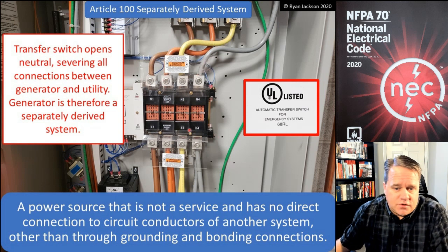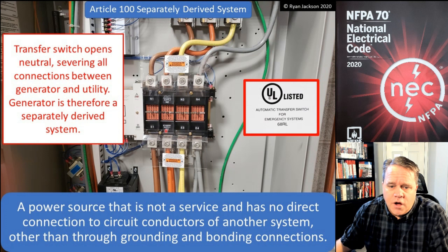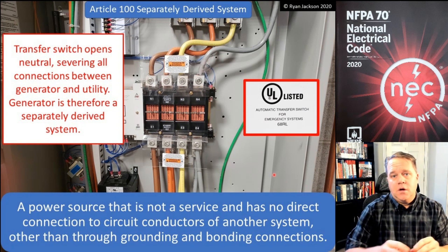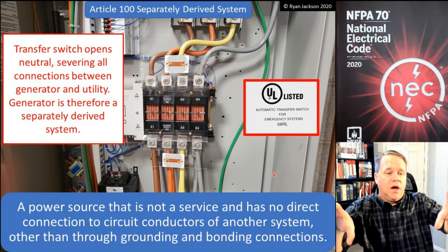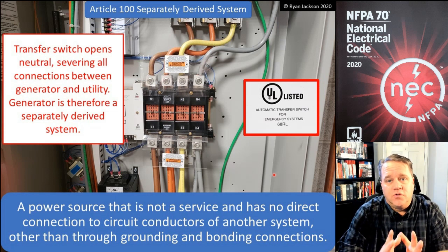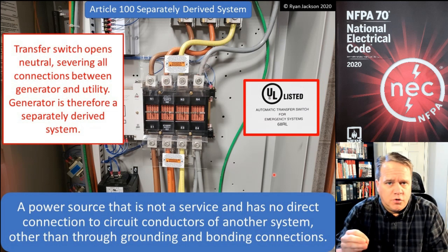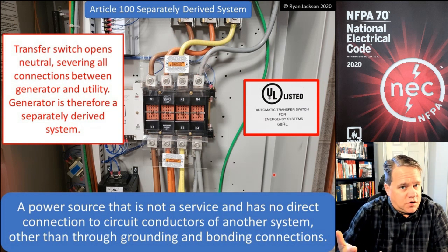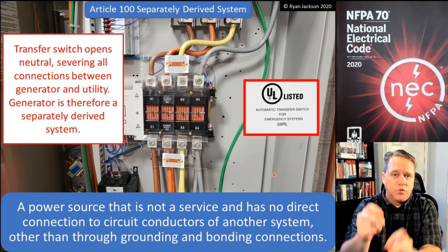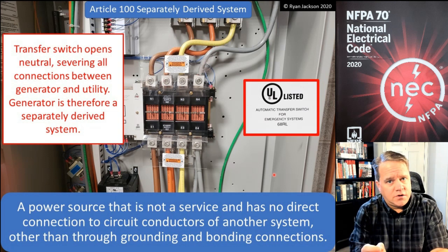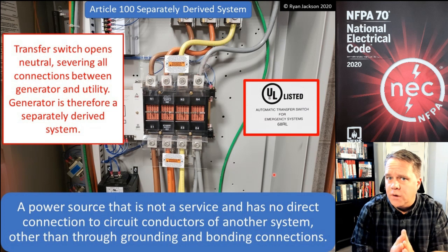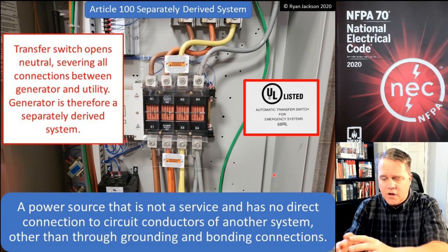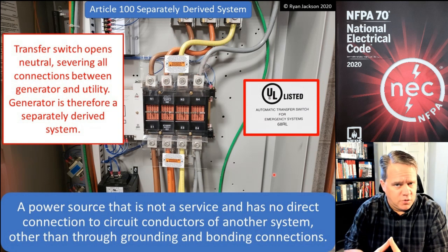Look at this transfer switch — it switches all three hots and the neutral. Because it switches the neutral, there is no connection between the generator on one side of the switch and the utility on the other side. That makes it a separately derived system. When the neutral is switched, or when there's no neutral at all, you have a separately derived system. That means you must connect neutral to frame at the generator, create a grounding electrode system, and follow NEC 250.30(A) — including installing a system bonding jumper.